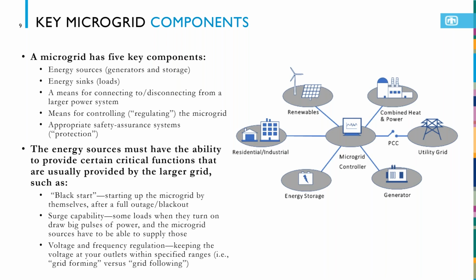Most of the time that's done off grid just to make sure you are operating, and everything starts to get coordinated from there. And then pre-negotiation with the local utility to ultimately get into resynchronization. Let's say the utility grid comes back on, you have to resynchronize. You can't just turn on that PCC switch anytime. Otherwise, you have surges and arcs and all sorts of things. You have to be very careful on how to do that. So that's the PCC, and you have to have that black start capability.